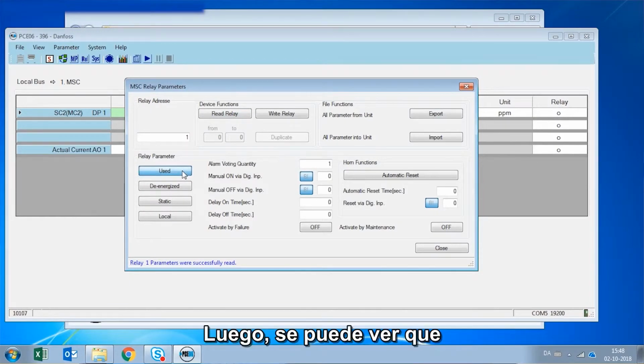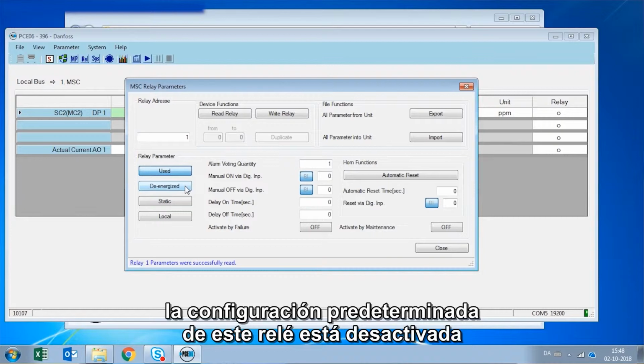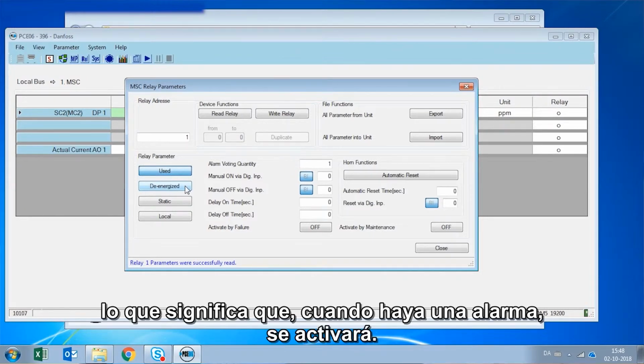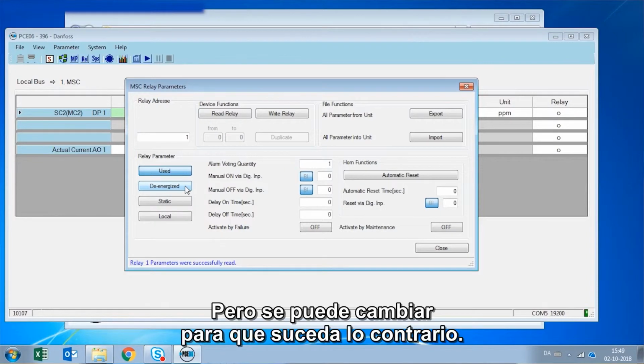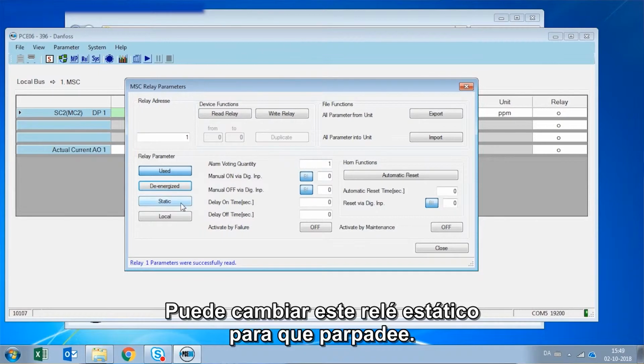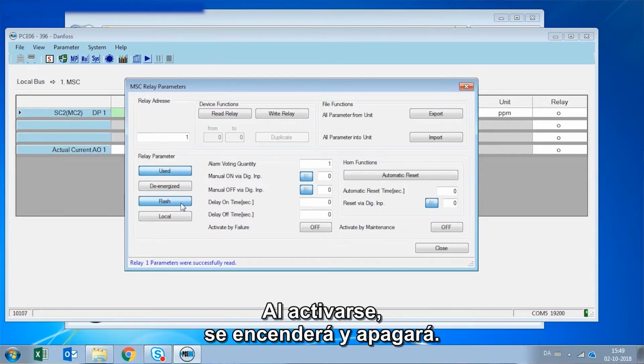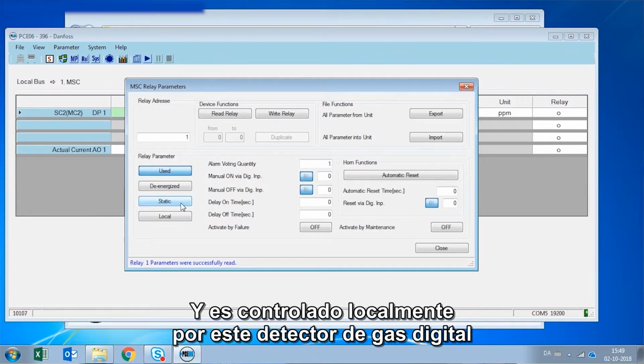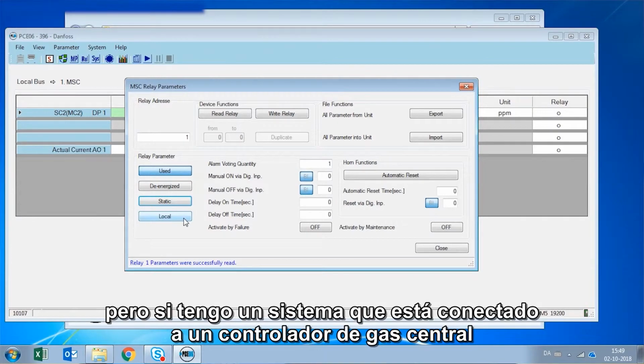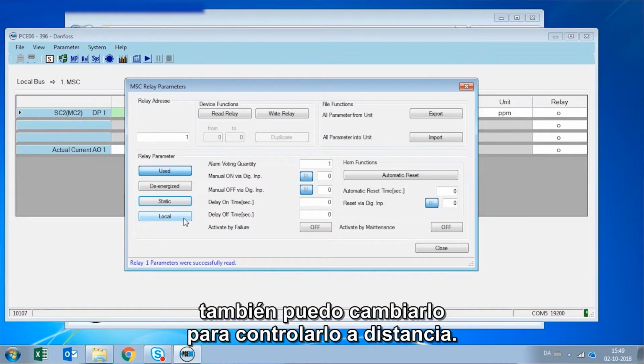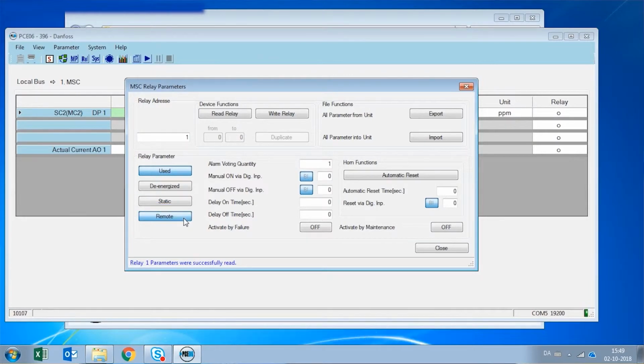Then you can see that the default setting of this relay is de-energized, which means that when there is an alarm, it will energize. But we can change that to be the opposite. It is a static relay, but I can change it to be flashing. So when it activates, it goes on and off. And it is controlled locally by this digital gas detector, but if I have a system that is connected to a central gas controller, I can change that to be controlled remote also.